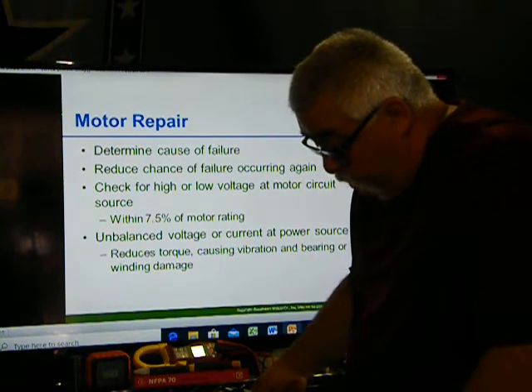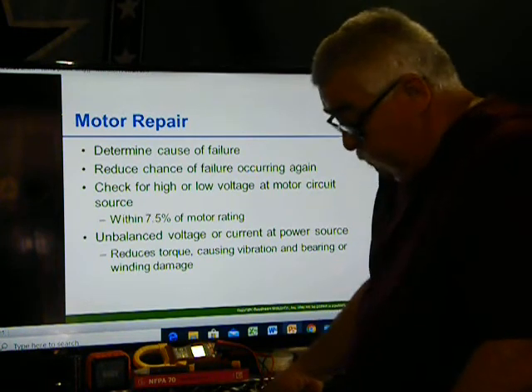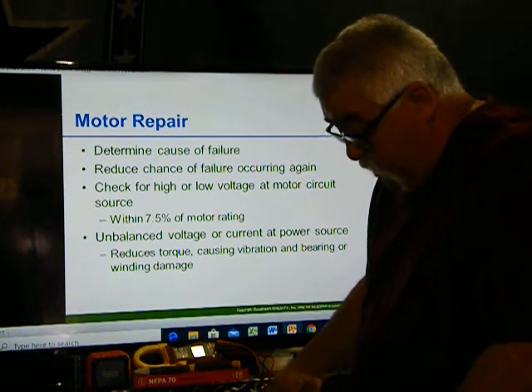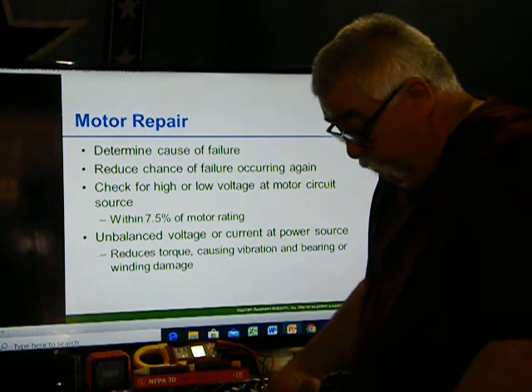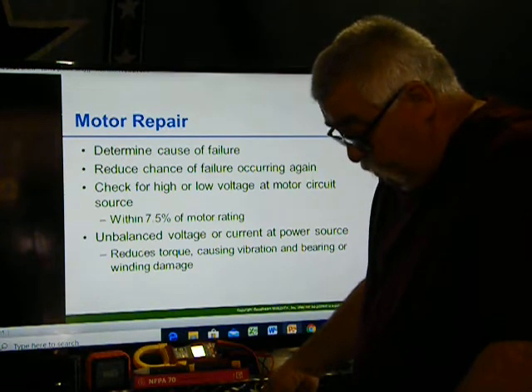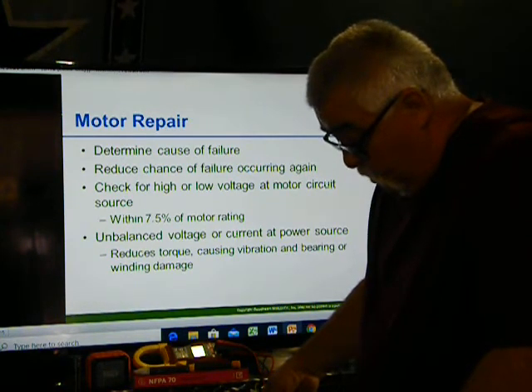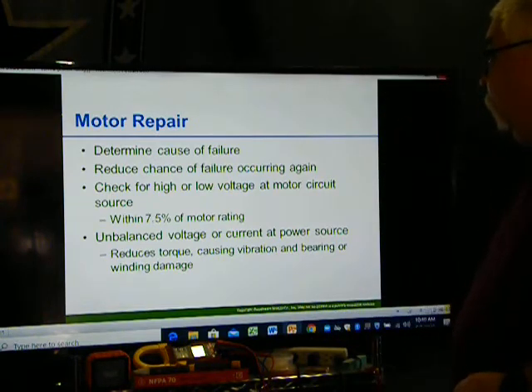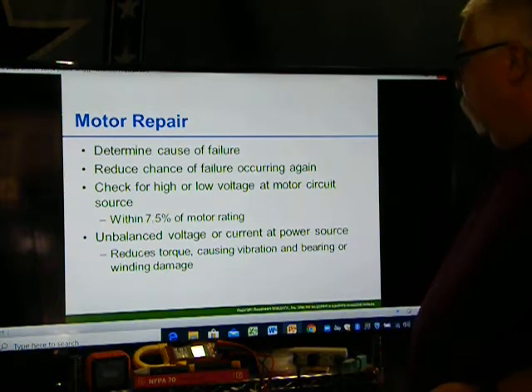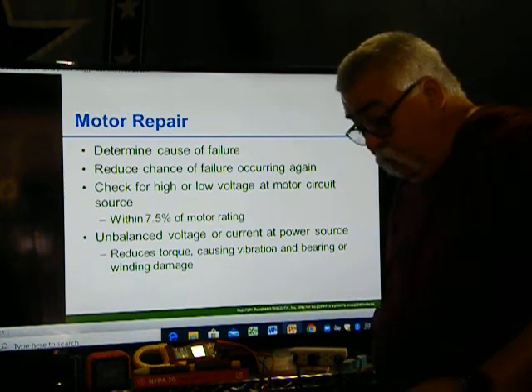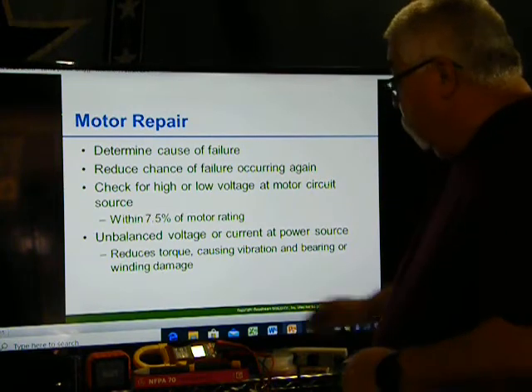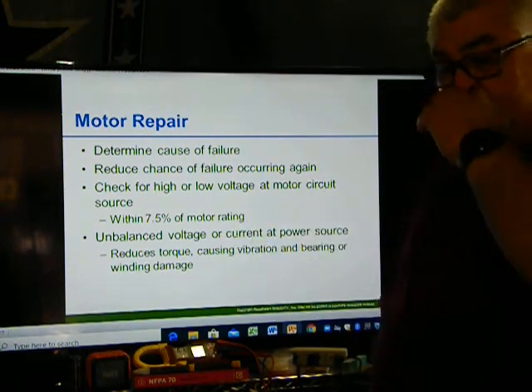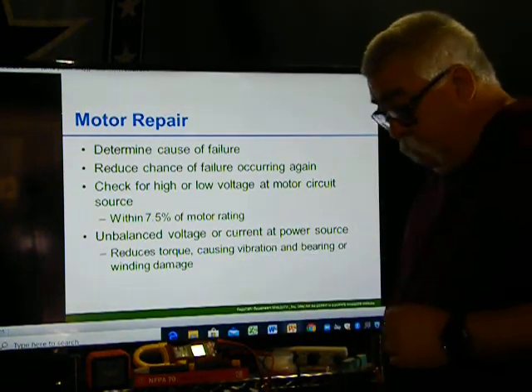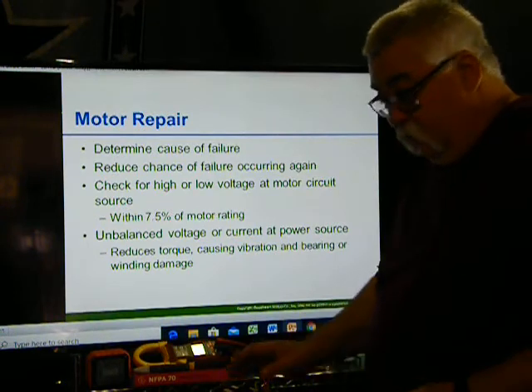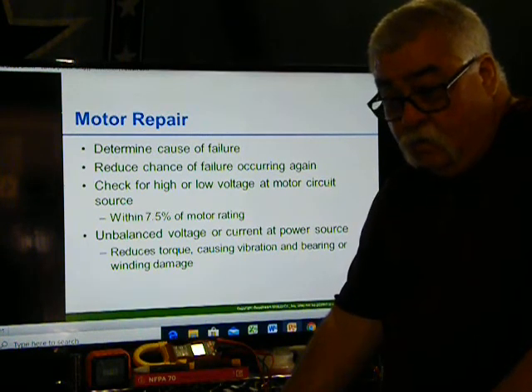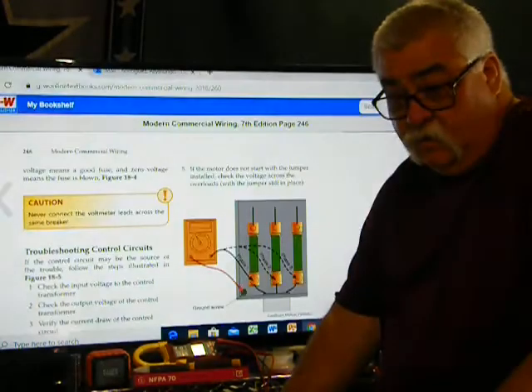In general, motors may fail for one of the following reasons: high or low voltage, unbalanced voltage or current at the source, excessive load, overheating, single phasing, excessive cycling, excessive moisture, and motor control center problems. Okay, so checking for high and low voltage at the motor source. Check your high and low, so we just did that. And then motor source voltage should also be within 7.5% of the motor rating. This breaks it down instead of like the book. So the PowerPoint is nothing like the book.